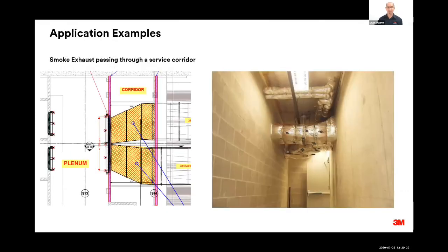Just to finish up, a couple of pictures of some application examples. Here we've got a smoke exhaust that's passing through a corridor, and so we need to enclose this duct because it has to stay open, it can't have dampers. And in the event that people are egressing through that corridor, fire couldn't break out of that duct. So it's all contained through the methods of dealing with the penetration on the concrete and blockwork wall, and insulated with 3M duct wrap, 615 plus duct wrap.